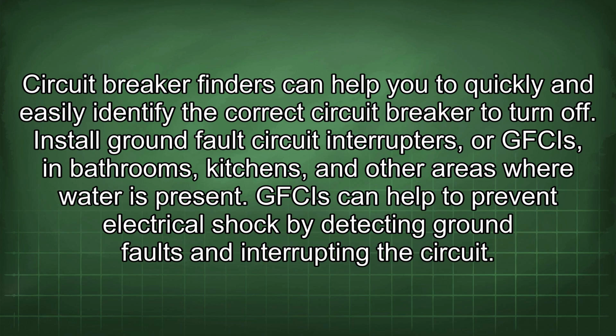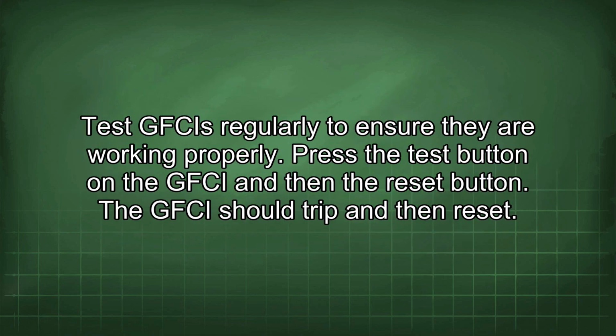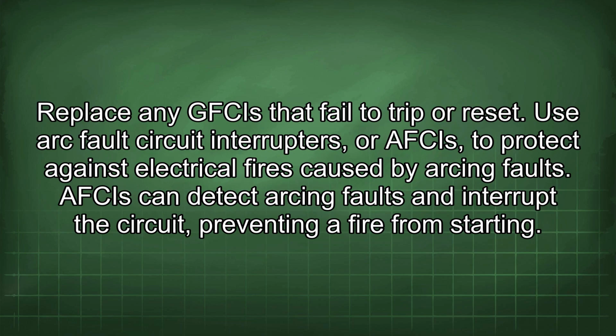Install ground fault circuit interrupters, or GFCIs, in bathrooms, kitchens, and other areas where water is present. GFCIs can help to prevent electrical shock by detecting ground faults and interrupting the circuit. Test GFCIs regularly to ensure they are working properly. Press the test button on the GFCI and then the reset button. The GFCI should trip and then reset. Replace any GFCIs that failed to trip or reset.